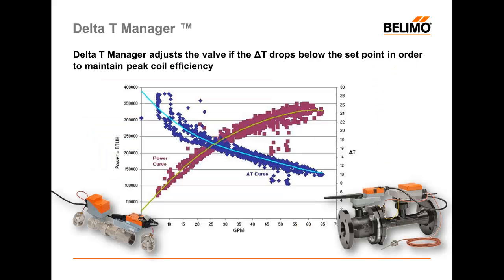The Delta-T manager adjusts the valve if the Delta-T drops below the setpoint in order to maintain peak coil efficiency. As an example, suppose that we determine the optimum Delta-T is 12 degrees Fahrenheit, and we have programmed the energy valve and the Delta-T manager to not let that Delta-T drop below 12°F. If the Delta-T does drop below 12°F, we will see the following response.